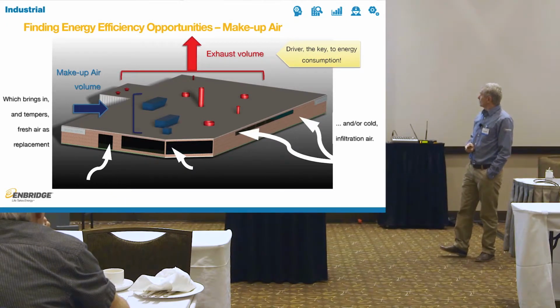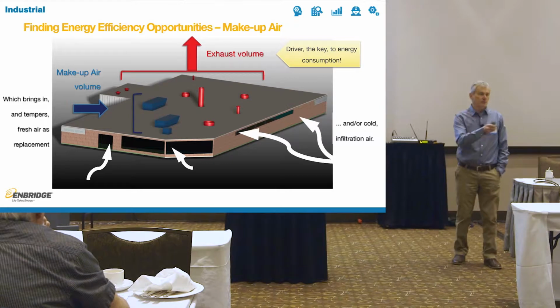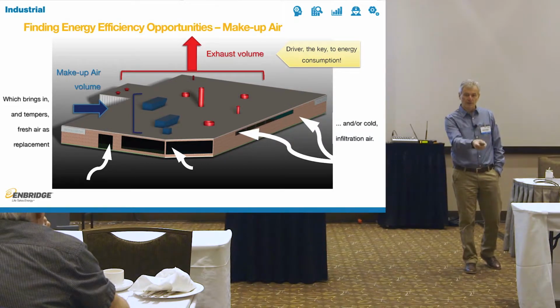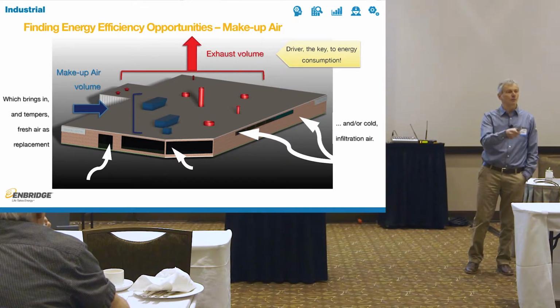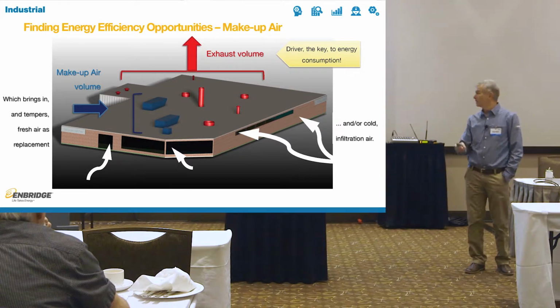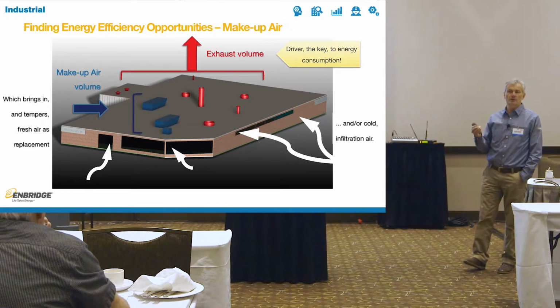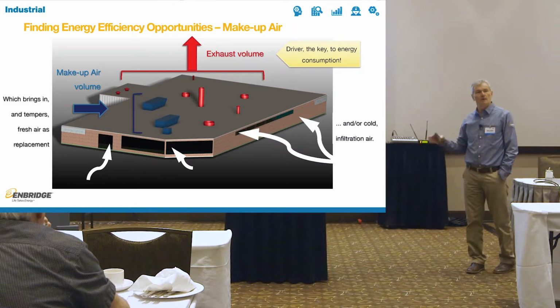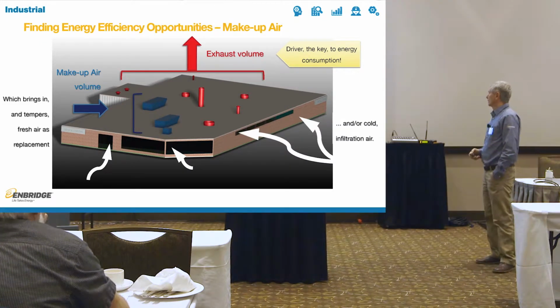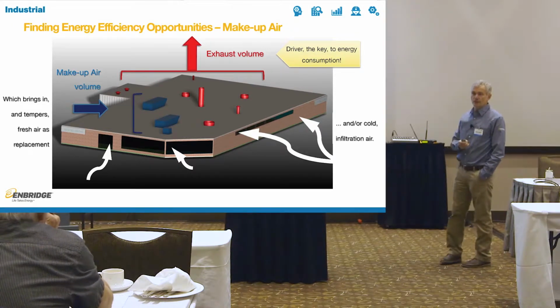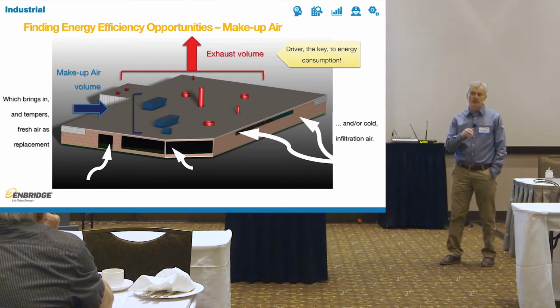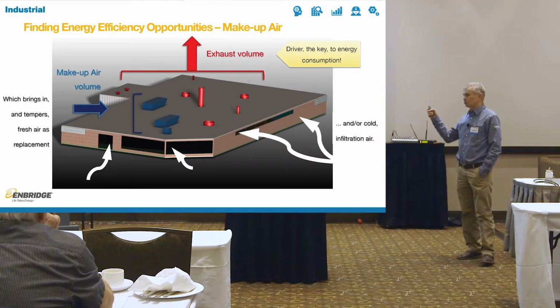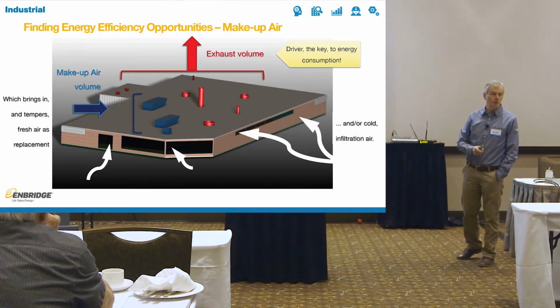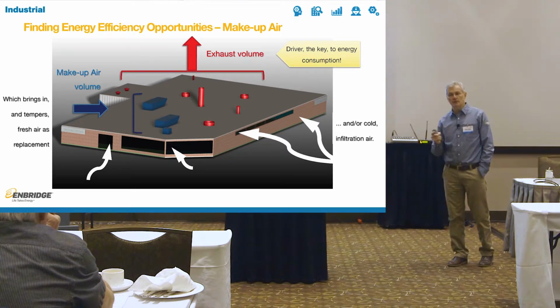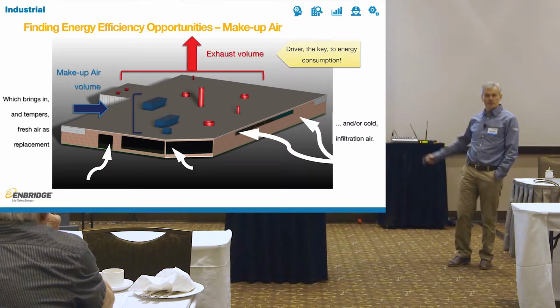So we said that exhaust volume drives the processes. Whatever processes you have, usually on their drawings, when they supplied you originally all these fancy processes, they put how much exhaust they require, each one of them. So that's your exhaust volume out of the facility. That's what you should be exhausting. Add 10% if you want to be safe or some such thing. But that's your exhaust volume needs. So whatever your exhaust volume is, now you have to bring that air in. So you need more. That defines your makeup air volume. If you have too little makeup air volume for the same amount of exhaust, the rest will be made up by the cold air that will infiltrate from all over the place. When you walk inside the facility and the door slams behind you, that's that infiltration working.